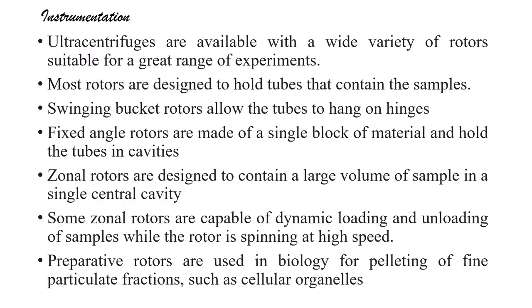Coming to the instrumentation of ultracentrifugation, ultracentrifuges are available with a wide variety of rotors which are suitable for a great range of experiments. Most rotors are usually designed to hold the tubes that will contain the samples. The swinging bucket rotors allow the tubes to hang on hinges, whereas the fixed angle rotors are made up of a single block of material and hold the tubes in cavities.